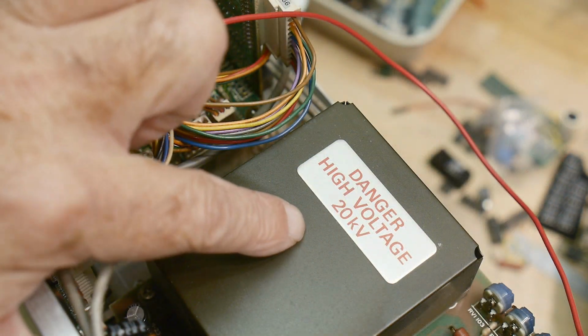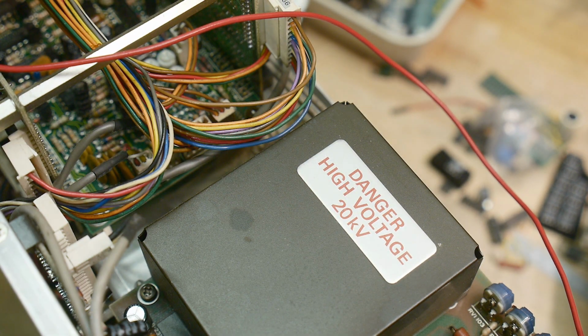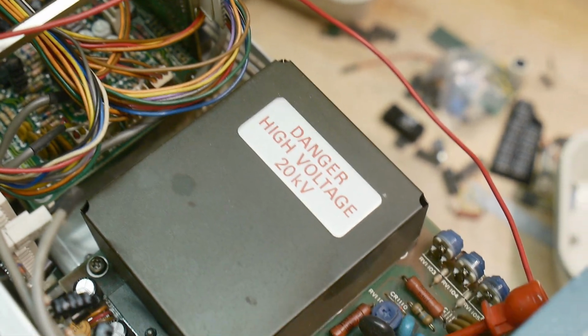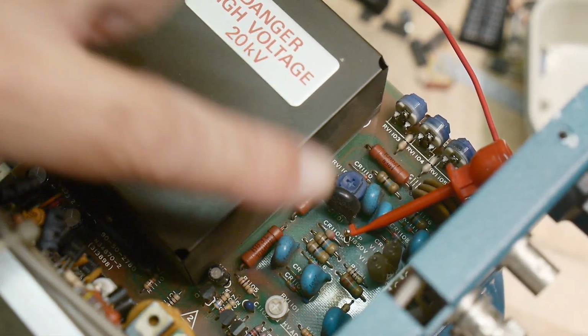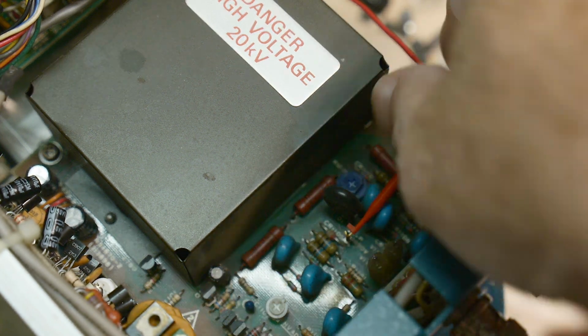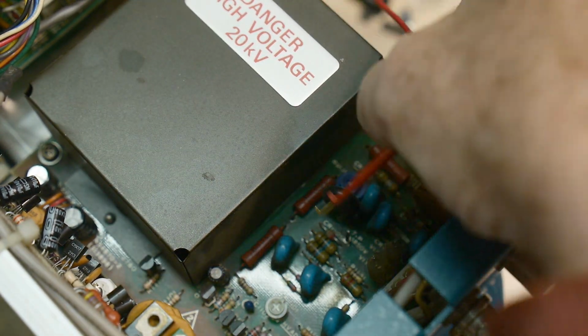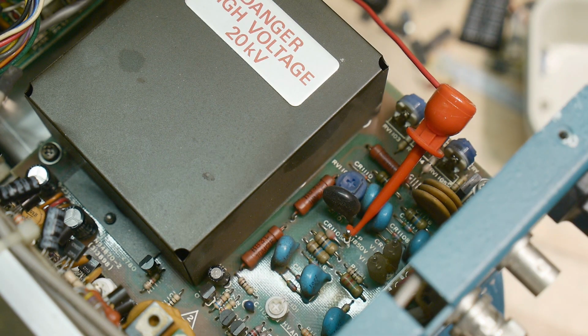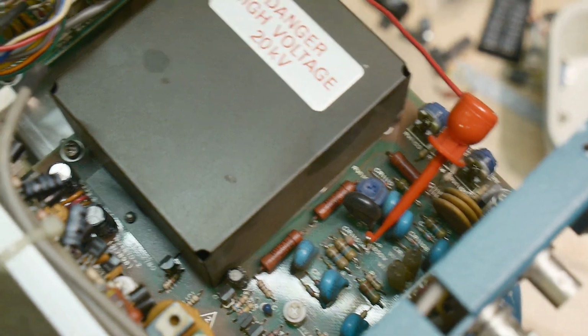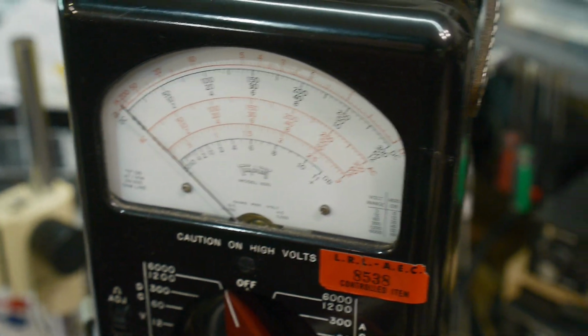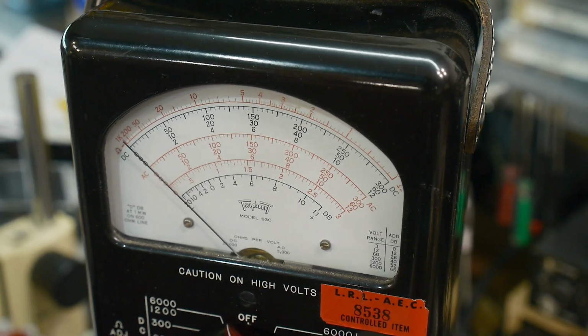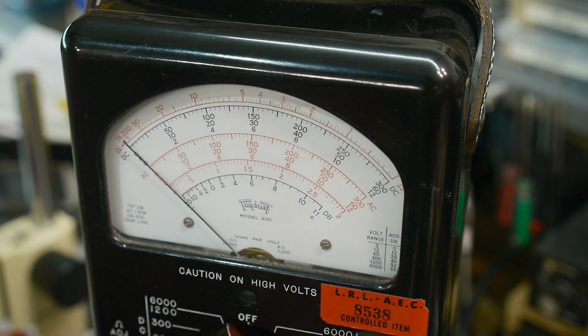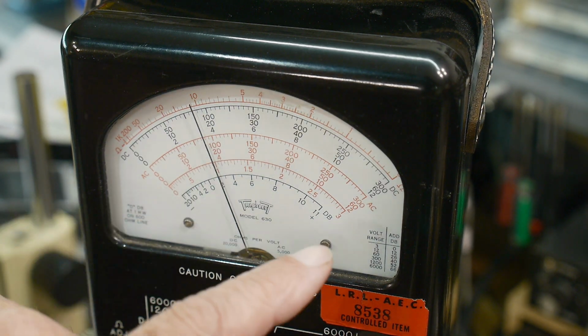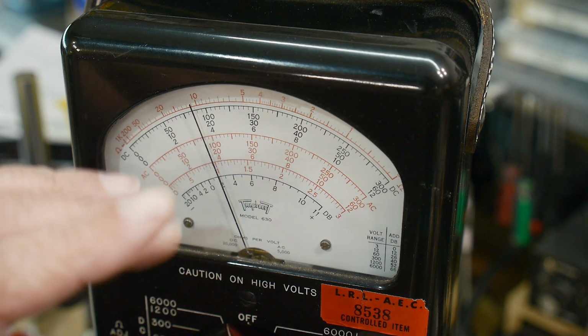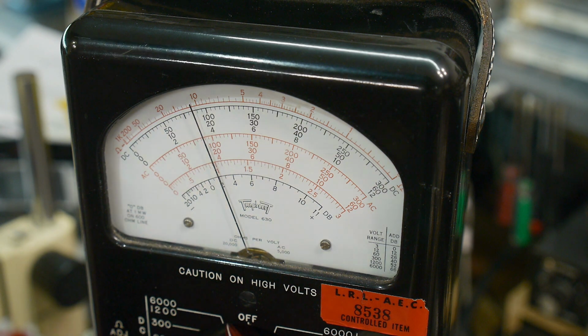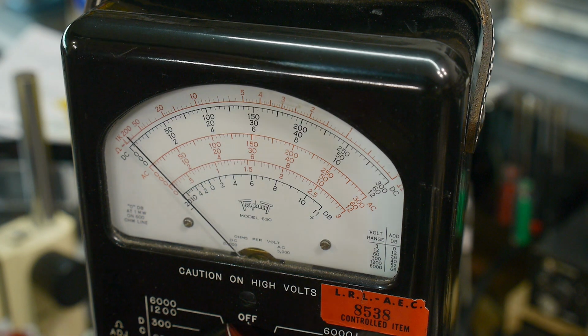All right, here's the high voltage section, 20,000 volts, 20 kilovolts. That's a lot. But there's a test point down here that's marked minus 1850. So I can measure that. I'll put my meter on it. I have a nice high voltage meter here. This goes to 6,000 volts. And let's turn it on and boom, there we go. So here's 2,000 volts. So we're measuring about 18. So I'd say that's probably pretty good.